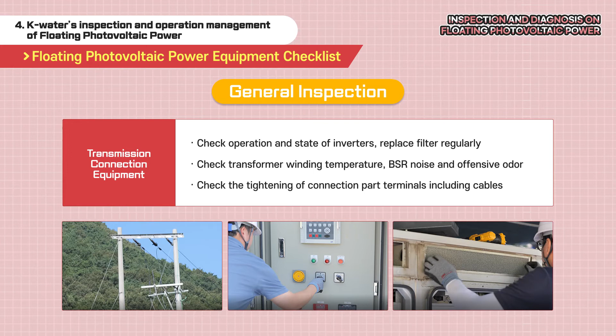As for the inspection of the power transmission connection equipment, the inverter operation and condition should be checked and the filter should be replaced regularly. Also, the winding temperature, BSR noises, and offensive odors should be checked. The tightening of the connection part terminals such as cable connection should also be checked. For your reference, KEPCO is a public company like K-Water that manages power generation in Korea.